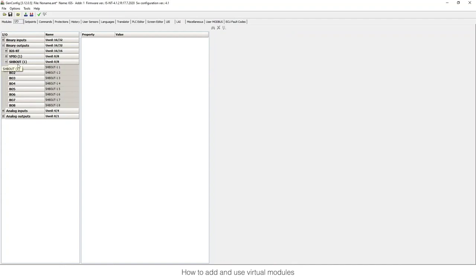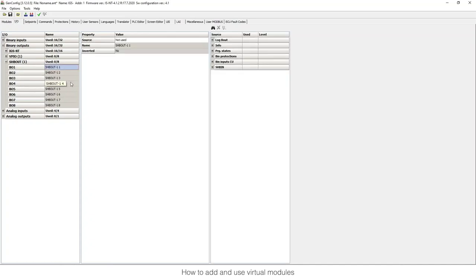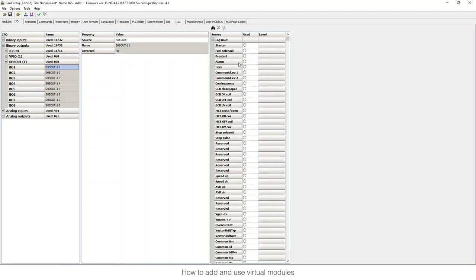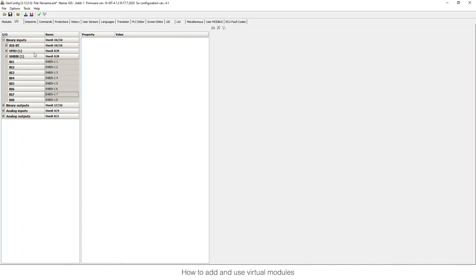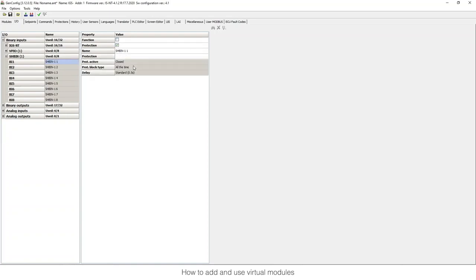I go to binary outputs and configure which outputs I want to send from the first controller. For example, I can send an alarm — I'll name it 'Alarm Controller 1'. Then in the second controller, I go to shared binary input one and connect the function or protection that reads when there is an alarm or warning from controller one. This information can be read by multiple different controllers.